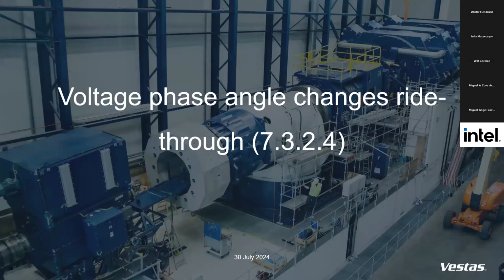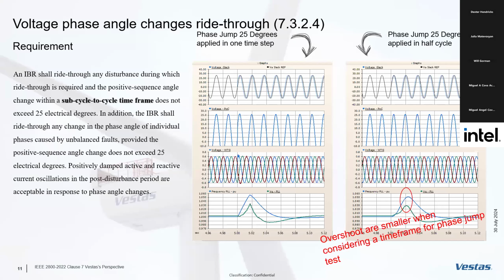So another important point is that clause 7.3.2.4 is another of the clauses that is creating some noise in the industry, and it's about the phase jump. Fortunately, for a type 4 machine that is our main technology, a phase jump is relatively straightforward when you don't have a direct coupled induction generator like a type 3 machine. Our main technology is the type 4 machine, so we can easily ride through the phase jump of 25 degrees. However, it's really important to keep in mind that the PLL is also configured to the specifics of the plant. That means that every plant will not have the same KPs and KIs on the PI of a PLL, so they will react differently to the same phase jump. So some of them will reach certain frequency or certain voltage that the other plant will not reach with the same technology, simply because it's configured in a different way.